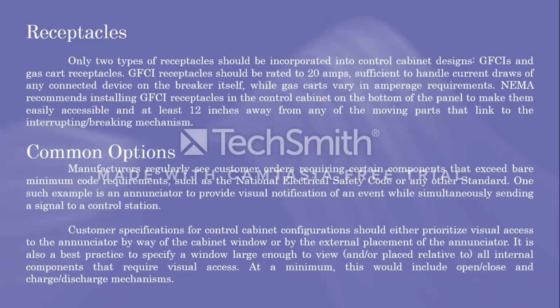So, common options. Manufacturers regularly see customers' orders requiring certain components that exceed bare minimum code requirements, such as the National Electrical Safety Code or any other standard. One such example is an annunciator to provide visual notification of an event while simultaneously sending a signal to a control station. Customer specifications for control cabinet configurations should either prioritize visual access to the annunciator by way of the cabinet window or by the external placement of the annunciator.